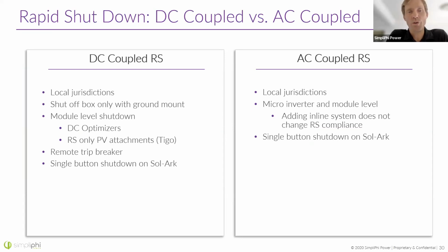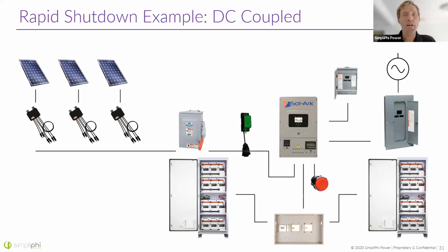When the solar's on the roof, you're required to have rapid shutdown modules on the roof. For an AC coupled system, those microinverters act as that rapid shutdown, so they have that compliance. Here's an example with DC coupled and rapid shutdown modules.